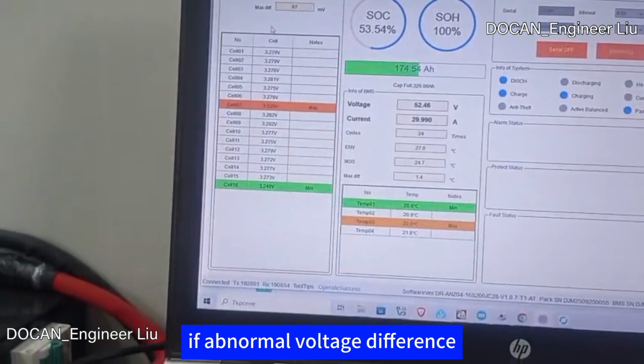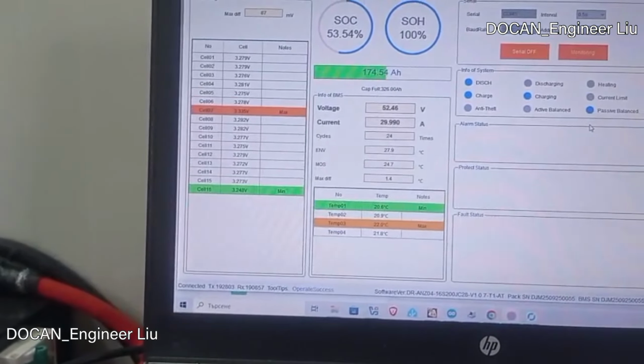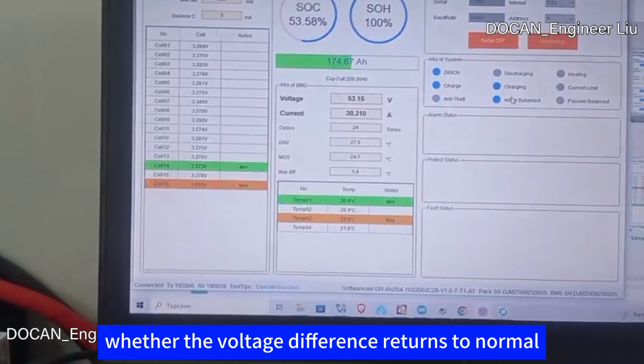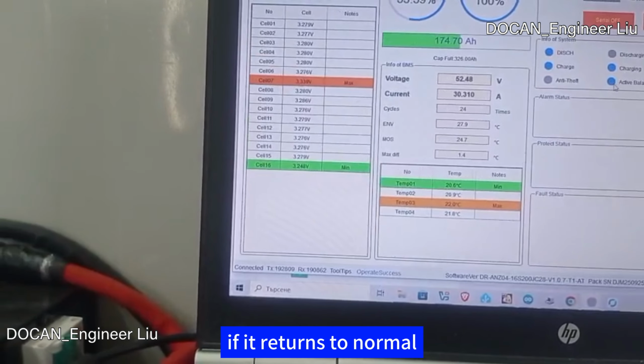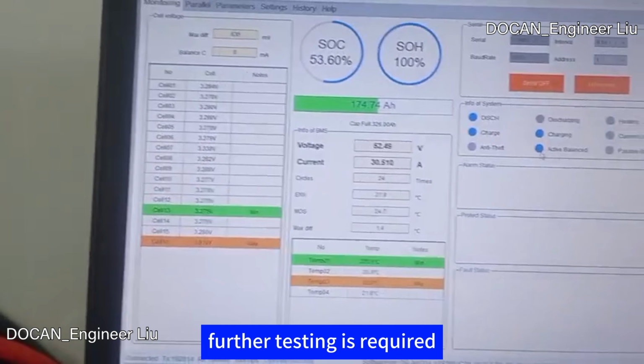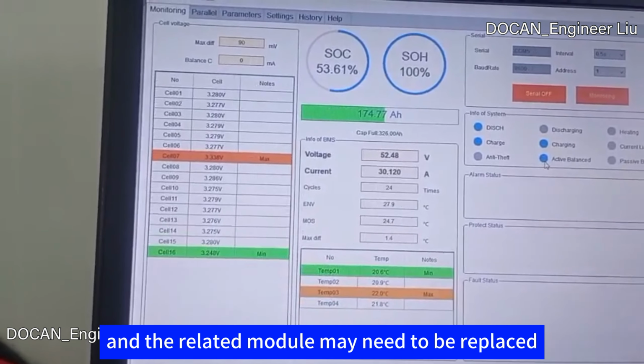If abnormal voltage difference appears after balancing starts, turn off the balancing function and check whether the voltage difference returns to normal. If it returns to normal, the balancing module may have a problem. Further testing is required, and the related module may need to be replaced.